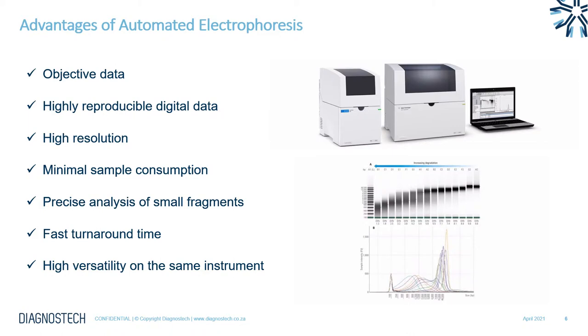This brings us to some of the advantages of an automated electrophoresis system such as the TapeStation. It generates objective data measured against markers and ladders of known concentration and size, and produces highly reproducible digital data. The systems enable very high resolution separation between fragments, down to a single digit of base pairs. Only minimal sample consumption is required — about 1 to 2 microliters of your precious sample — allowing precise analysis of very small fragments. Both systems have a very fast turnaround time, taking less than 1 minute per sample analysis, and provide high versatility on the same instrument, enabling measurement of multiple different parameters and different sample types.